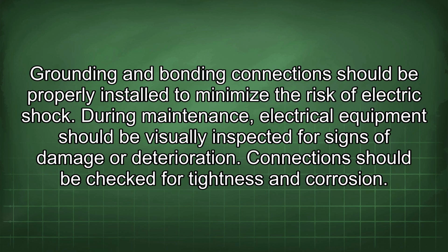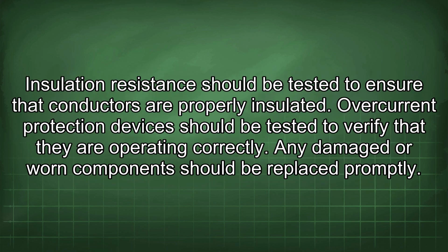During maintenance, electrical equipment should be visually inspected for signs of damage or deterioration. Connections should be checked for tightness and corrosion. Insulation resistance should be tested to ensure that conductors are properly insulated. Overcurrent protection devices should be tested to verify that they are operating correctly. Any damaged or worn component should be replaced promptly.